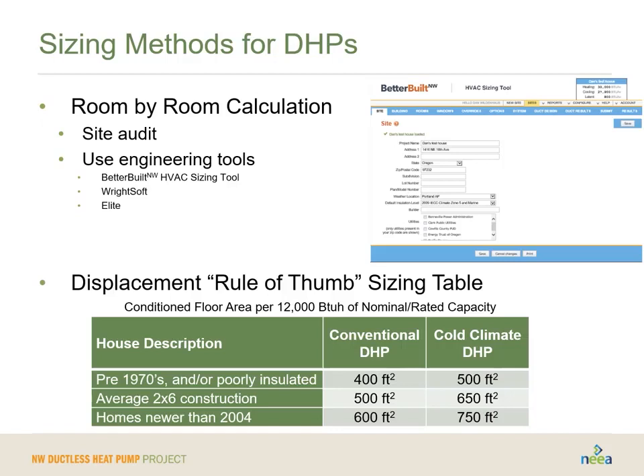As we look at either more complex or we really want to solve more than one room's condition at a time, we really need to do room by room calculations for how much heat is lost over the course of the day. This is really going to allow us to put the right size system and then select the right equipment to meet that goal. And there's several engineering tools available. One is the BetterBuilt Northwest HVAC sizing tool. You see a little screen grab of that in the upper right-hand corner. What's wonderful about this is it's free, and it will give you very similar answers as some of the other softwares, such as WrightSoft and Elite, which are terrific pieces of software. They do a lot of really good things there, but they do have some pay associated with them.